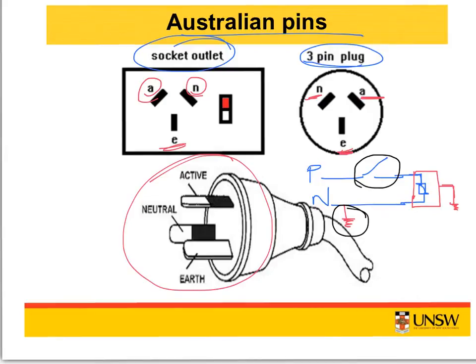So consider a scenario where the active wire gets accidentally connected to an ECP on a piece of equipment. So let's say here this active wire gets connected to the ECP accidentally. Now this creates a shock hazard. However, since the ECPs are connected to the ground through the third pin, as you can see here, the active wire becomes connected to the grounding wire. So basically we are connecting the active wire through the grounding wire. Now the neutral wire is also connected to the grounding wire at the circuit breaker panel, which is here.